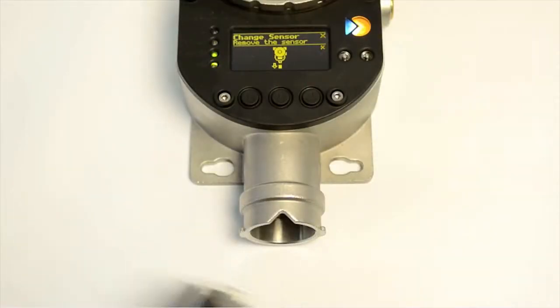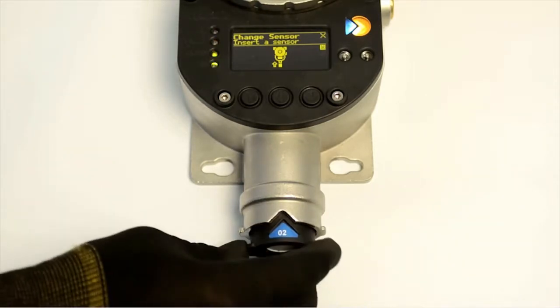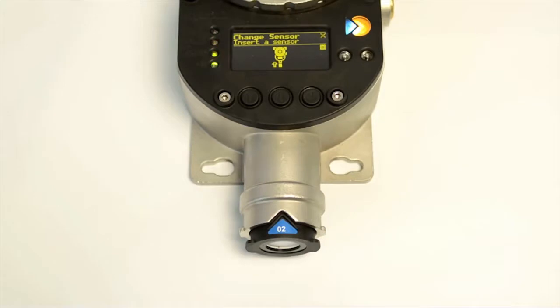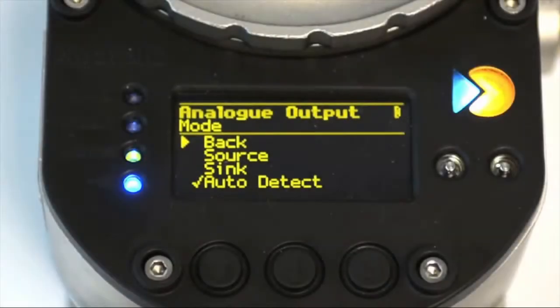X-Guard IQ avoids the bureaucracy and disruption of hot work permits which are not required to change a sensor. They're very quickly and easily removed and a pre-calibrated replacement sensor can then be slotted into place. With the new sensor installed and the detector back online, the old sensor can be taken to a safe environment for calibration.